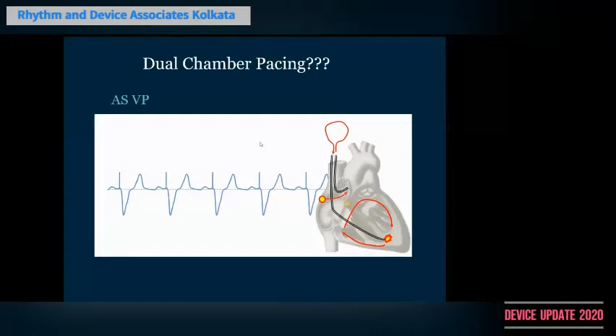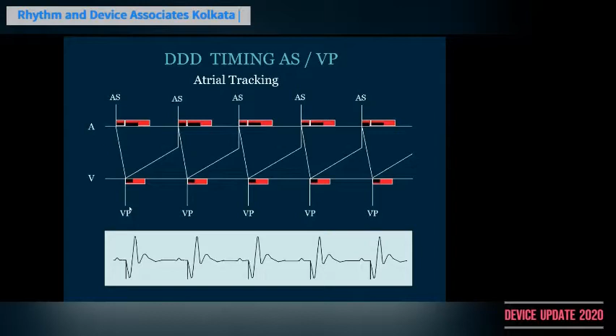After the ventricular pacing spike is given, there is a ventricular blanking period and a ventricular refractory period, and there is a corresponding atrial blanking and atrial refractory period in the atrial channel as well. This is called post-ventricular atrial blanking and the post-ventricular atrial refractory period. So these 2 refractory periods are set off in the 2 chambers after initiation of a ventricular event, either sensed or paced. This is something that you have to conceptually remember all the time. A ventricular event gives rise to 2 different sets of refractory periods in the 2 chambers.